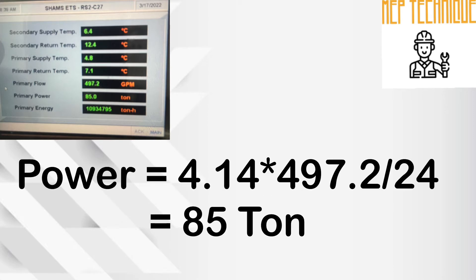So now we will put this formula to calculate the power. We multiply 4.14 with 497.2 and divide by 24. The result is 85 ton. If we check the ETS meter reading, it is also 85 ton.